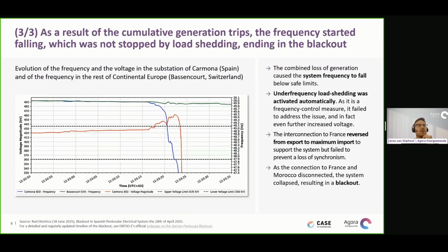The final stage, and I said there were three, the third stage was the actual runaway into blackout. So even though it wasn't a frequency problem initially, because of these cumulative generation trips, the frequency starts to fall because there is a shortage of supply now. And the system operator has automatic load shedding defense plans that were activated to try and manage this. But it wasn't a frequency problem that was underlying it, so these things didn't work. In fact, they made things worse because as you shed load, it typically further increases the voltage.